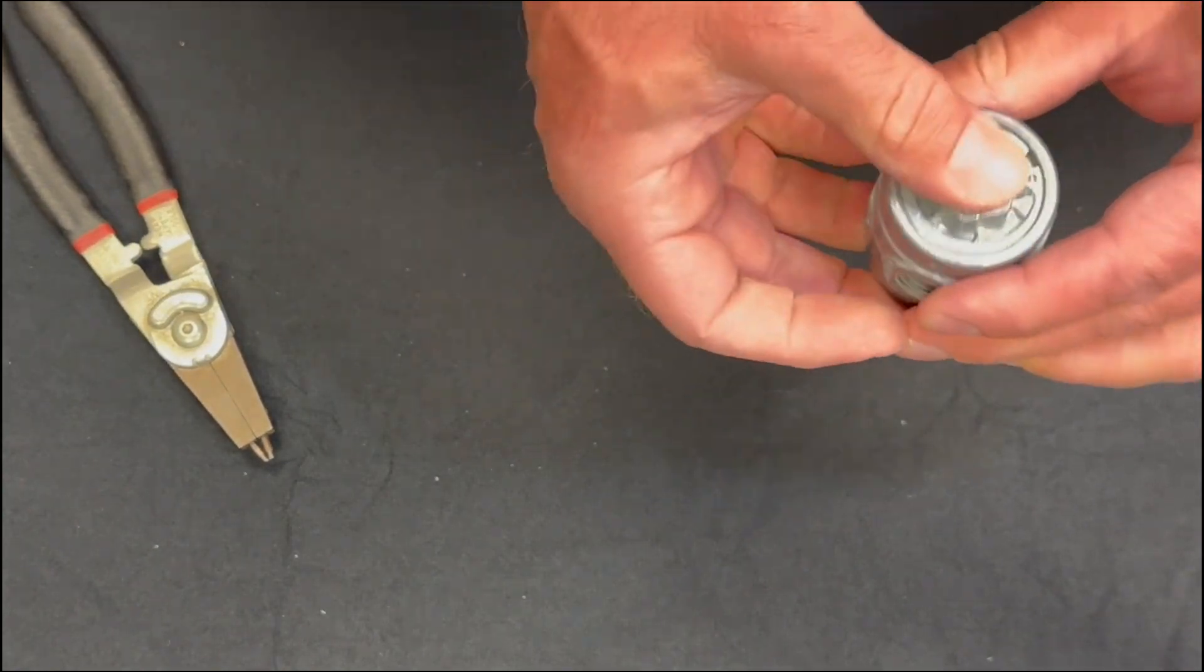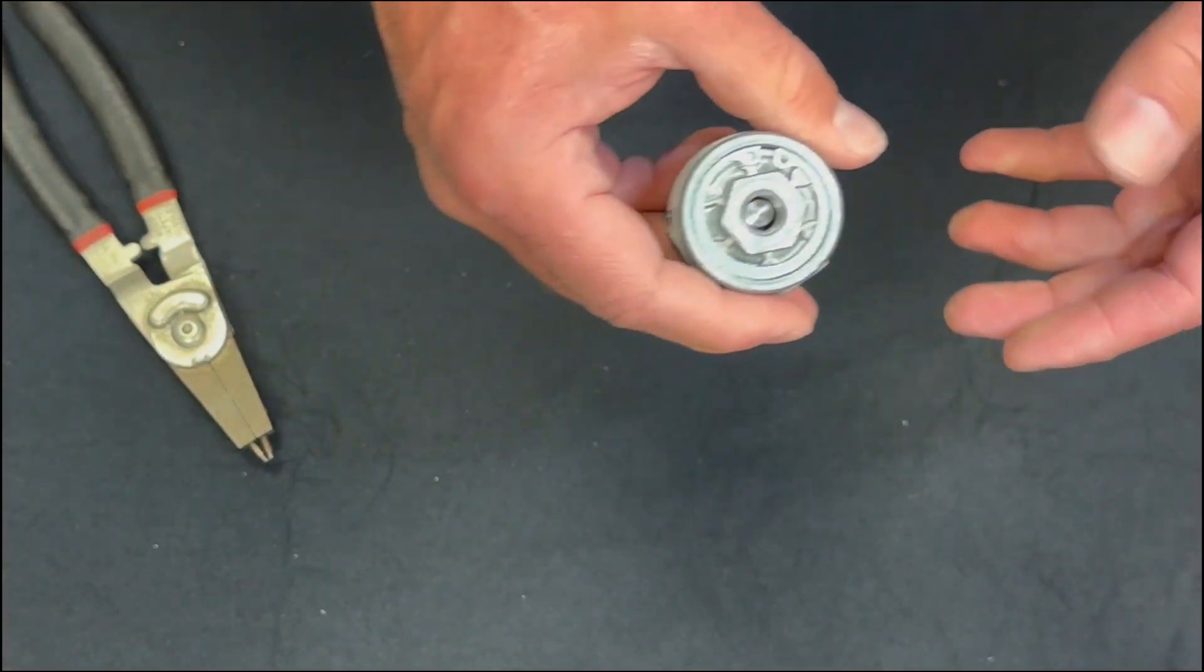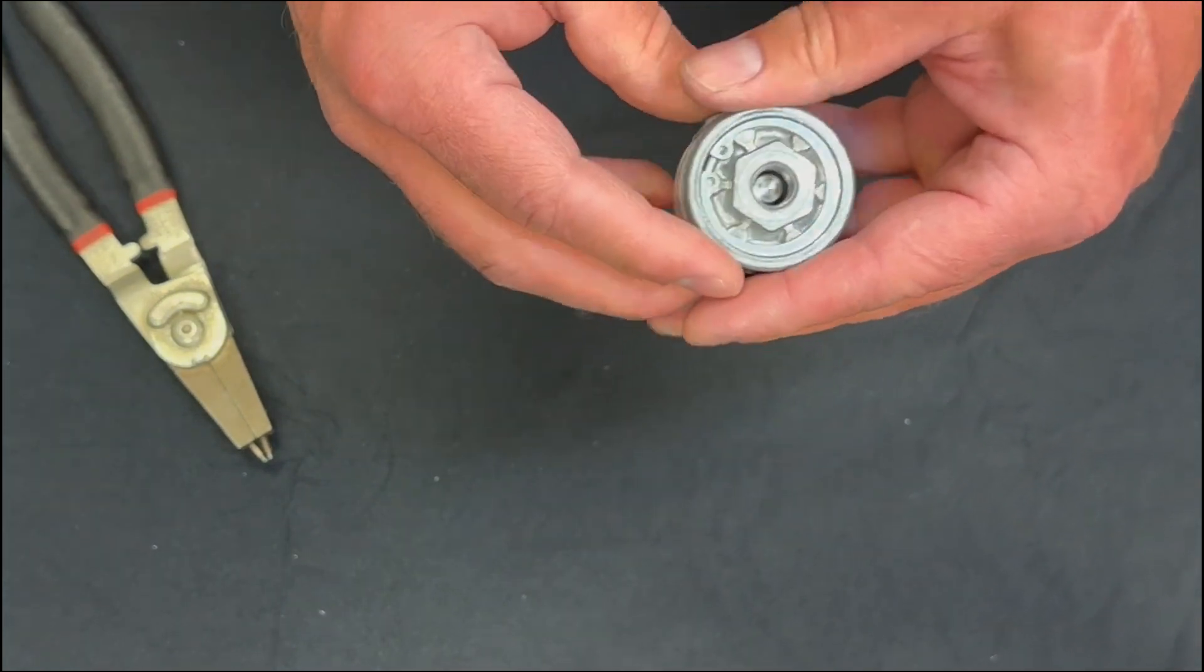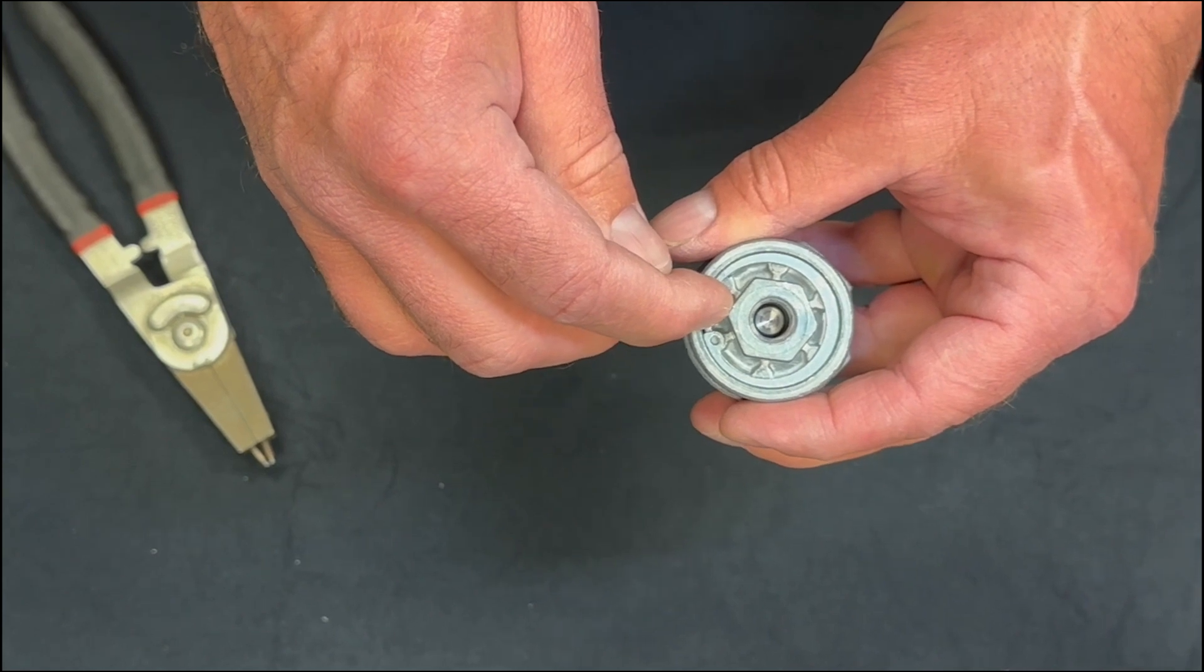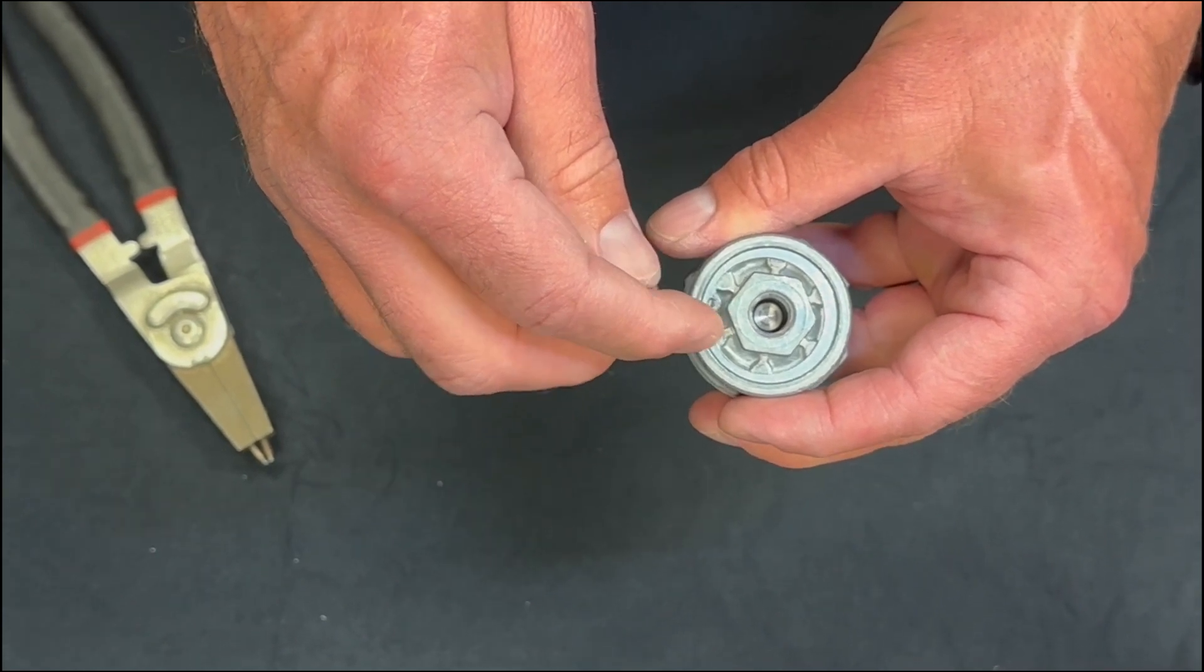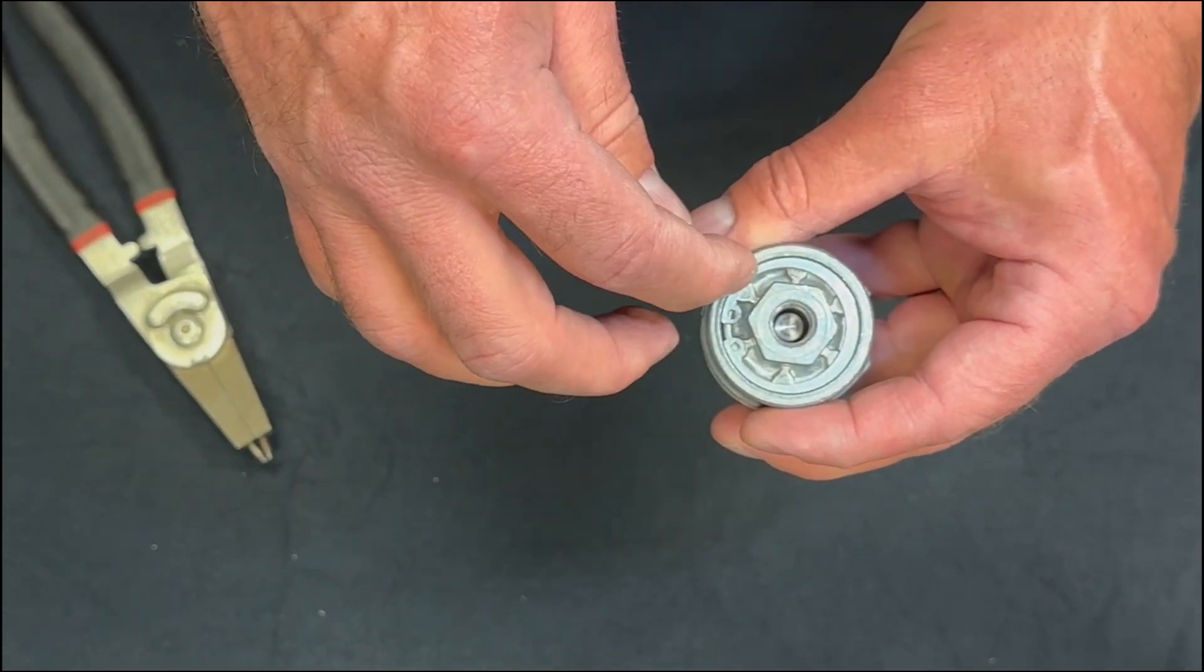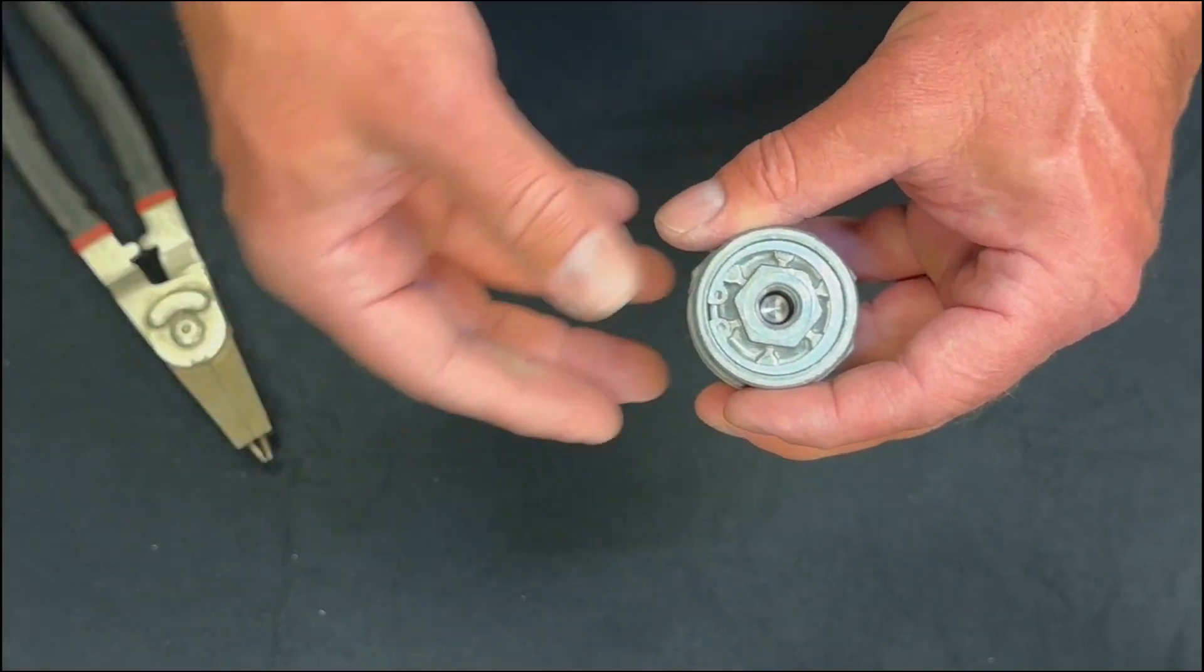Once everything is back in place, go ahead and reinstall the pilot valve back onto the tank, making sure that you hold a backup on the top cap of the pilot valve in order not to distort or destroy the diaphragm inside of the pilot valve and retest your system.